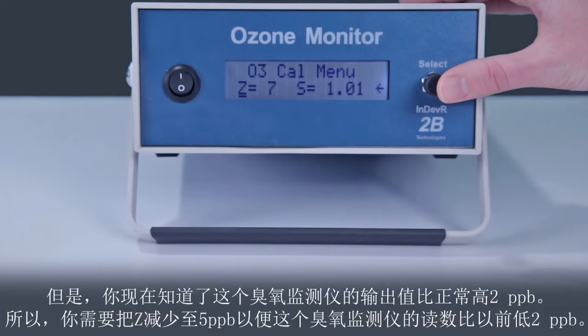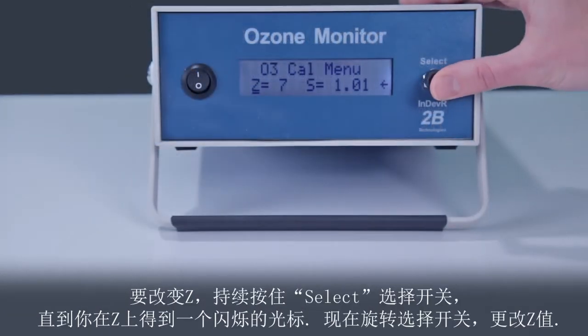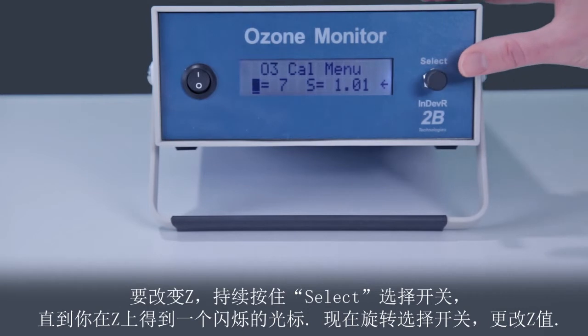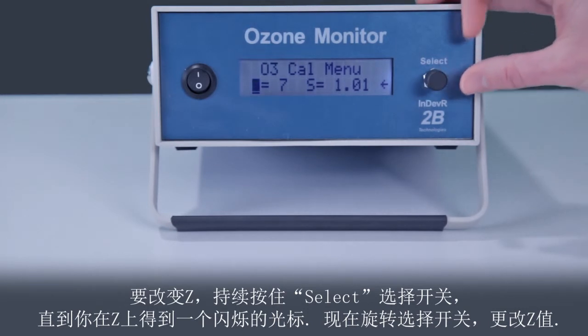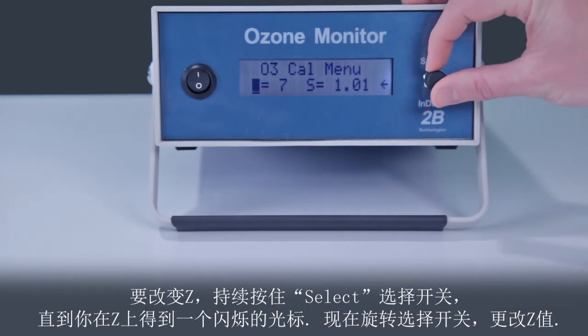But you now know that the ozone monitor is outputting a value too high by 2 ppb. So you need to reduce Z to 5 ppb in order to make the ozone monitor read 2 ppb lower than before. To change Z, hold in the select switch until you get a blinking cursor over the Z.